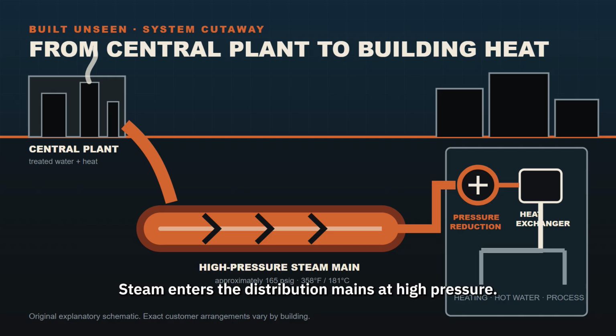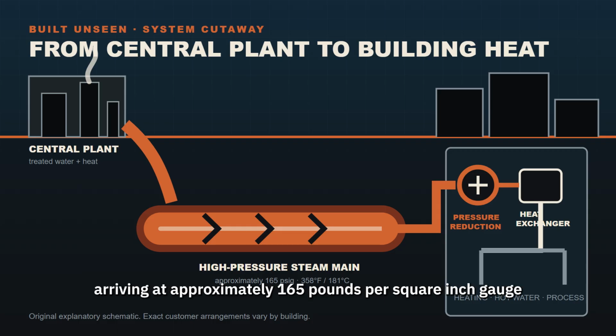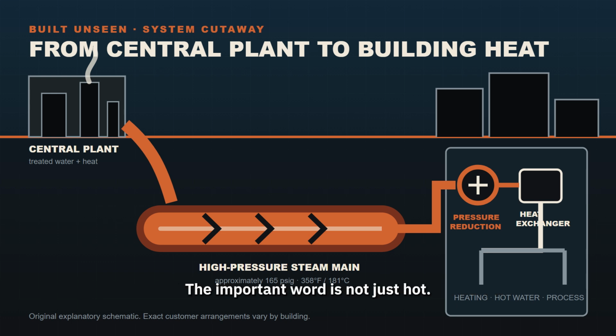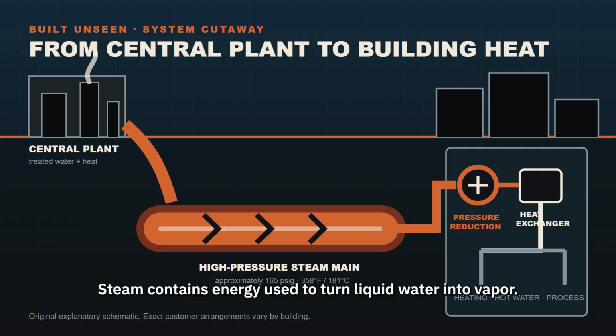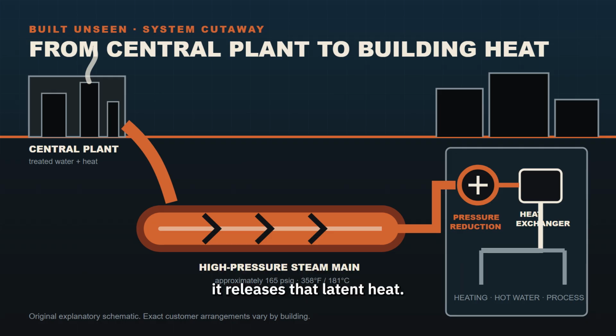Steam enters the distribution mains at high pressure. Con Edison's customer guidance describes saturated steam arriving at approximately 165 pounds per square inch gauge at about 358 degrees Fahrenheit, or 181 degrees Celsius. The important word is not just hot, it is phase. Steam contains energy used to turn liquid water into vapor. When that vapor reaches a building and condenses back into liquid, it releases that latent heat. This allows a comparatively small mass of steam to carry a large amount of thermal energy.